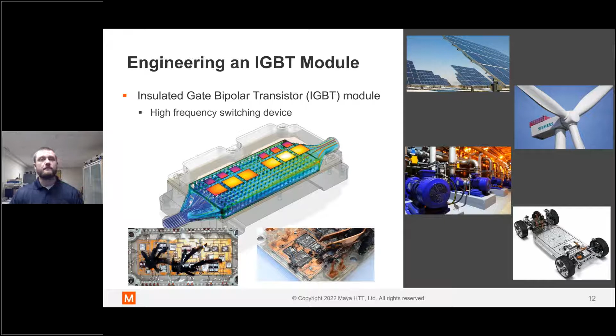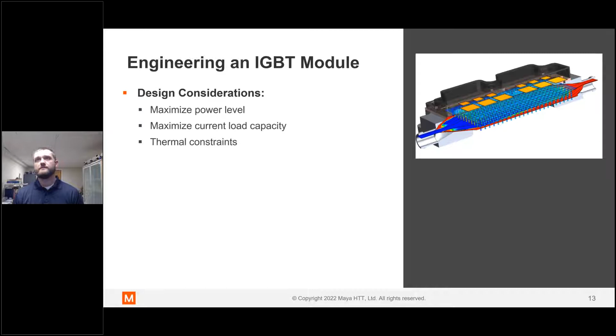In cooling systems like this, to keep things cooler you can increase the flow rate, which will drive the temperature down in the system and down to the chips. However, you'll suffer a higher pressure drop through the system, so you'll need a larger pump to drive your coolant - that's a trade-off. This is one of the classical heat exchanger design balances: you want to maximize cooling, but you also have to be careful not to increase the pressure drop so much that you need an enormous pump to drive it and lose a lot of energy there.